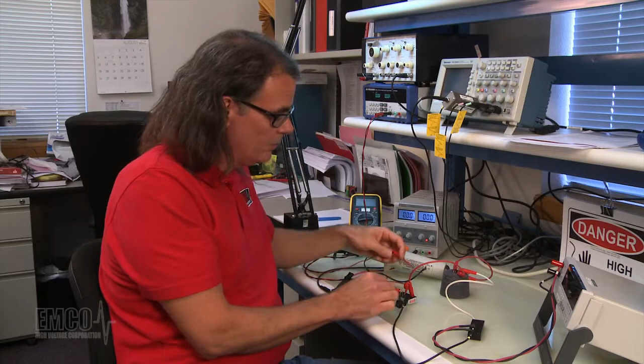As I mentioned, you can also monitor a low voltage representation of the high voltage output on the voltage monitor pin on the unit itself. This is a scaled down voltage that is in proportion to the output voltage, and the ratio of that voltage will vary from model to model, so you need to consult your data sheet to know exactly what that voltage will be. In this case, it's going to be a 0 to 5 volt. So again, I clip the return lead to the ground pin and then connect the positive lead to the voltage monitor pin on the CA unit. So the unit is configured and ready for test.